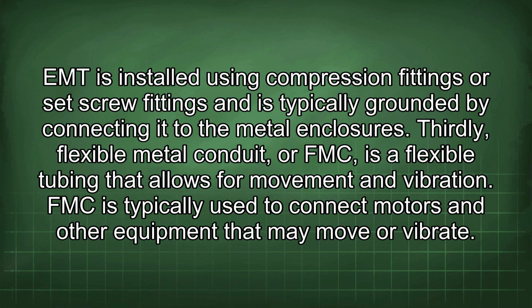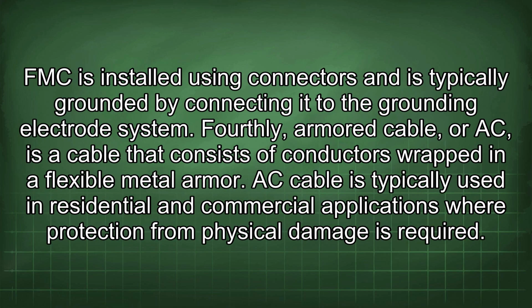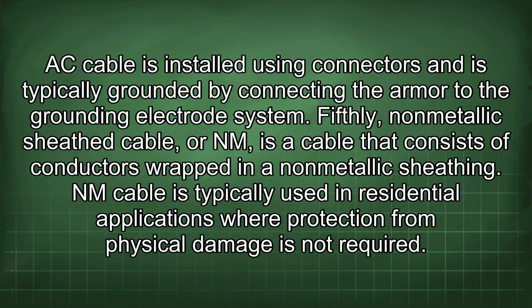FMC is typically used to connect motors and other equipment that may move or vibrate. FMC is installed using connectors and is typically grounded by connecting it to the grounding electrode system. Fourthly, armored cable, or AC, is a cable that consists of conductors wrapped in a flexible metal armor. AC cable is typically used in residential and commercial applications where protection from physical damage is required. AC cable is installed using connectors and is typically grounded by connecting the armor to the grounding electrode system.